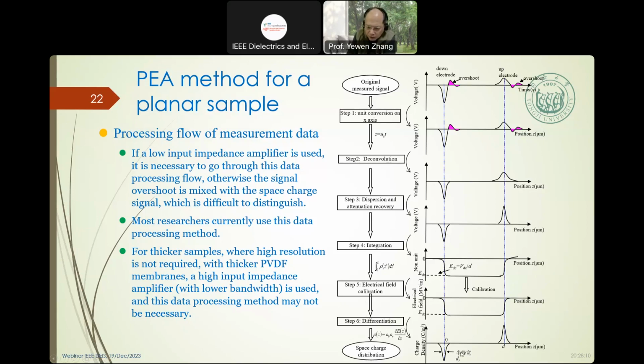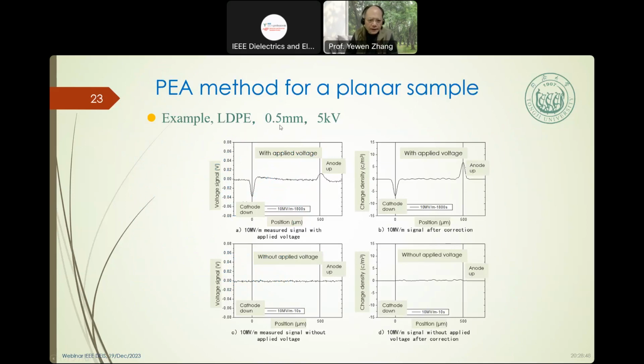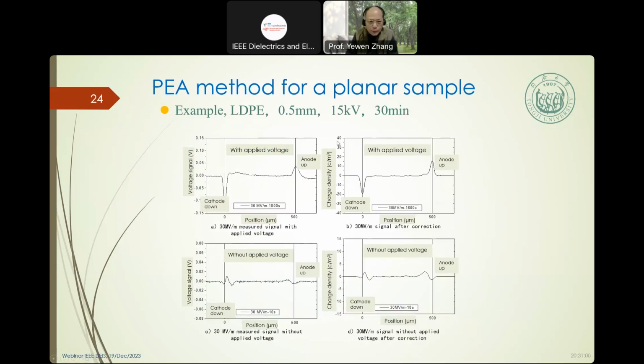Sorry, this is in Chinese. This resolution is very similar to the thickness of the PVDF film. So, for example, for LDPE of 0.5 millimeter with 5 kilovolts applied voltage, we can get the low field, so we get the signal without space charge. After some time, we apply 15 kilovolts. After 30 minutes, we get the space charge like this without applied voltage. So you see three peaks, but the second peak may not be a real interface charge. This one is the interface charge, this one the space charge. This one we cannot say is a charge or not. I think it is like noise here.